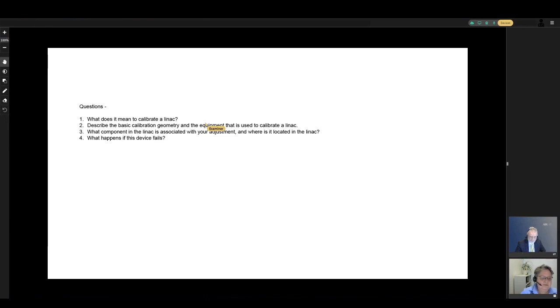Yeah, so you essentially need to re-verify your calibration. So you can recalibrate, verify everything is as you would expect it, or you can run some existing plans and measure the dose that they deliver and compare them with what you would expect. Or you can go in to service mode, you run 100 monitor units and make sure that the dose is equivalent to what you would expect from 100 monitor units.